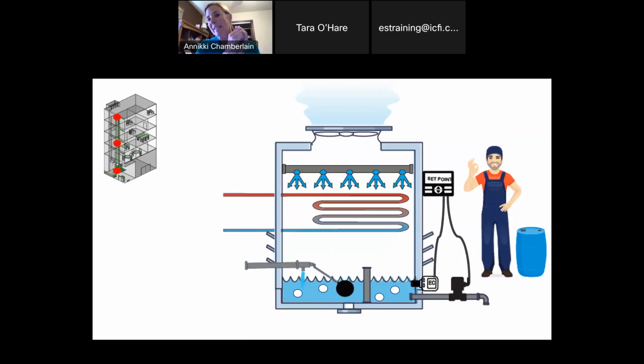So what we've done is basically taken that condenser where we're releasing the heat from the system and put it right into the tower here. We're running water right over that condenser. And then we've just broken up the compressor and the expansion valve or metering device. So pretty much the same failure points. With the chiller, you're going to get scale inside those tubes. On an evaporative condenser, you're worried about getting scale on the outside of those, the tube bundle inside of your tower. But again, we're talking the same failure points.